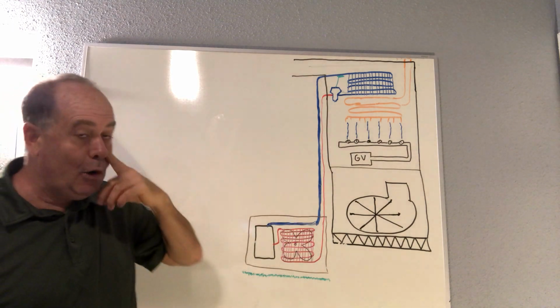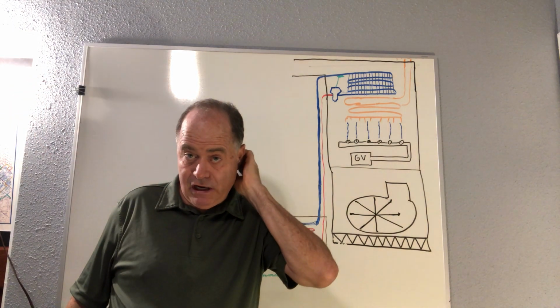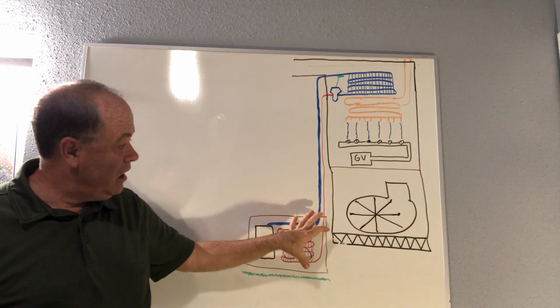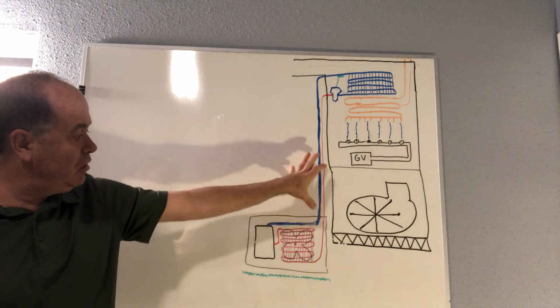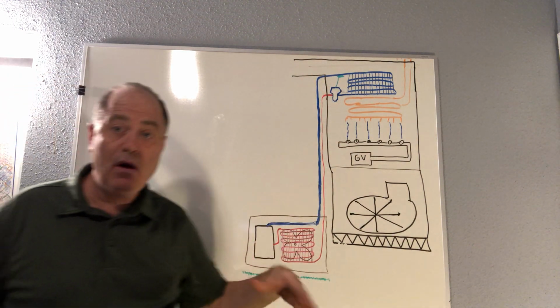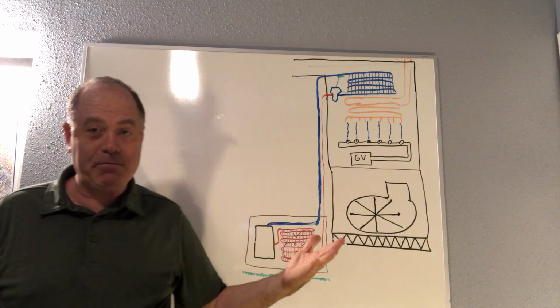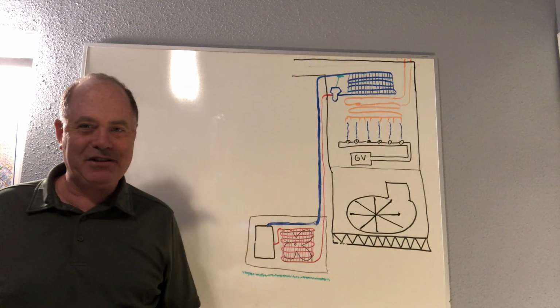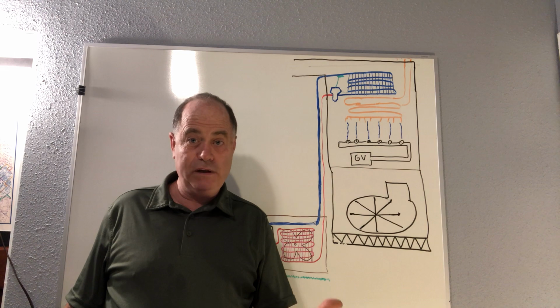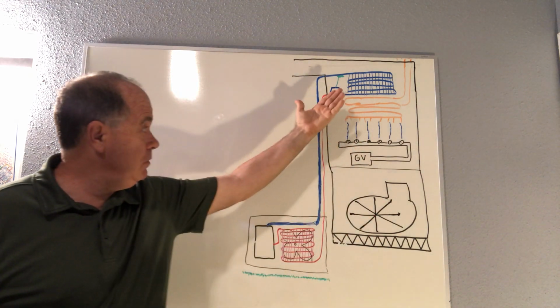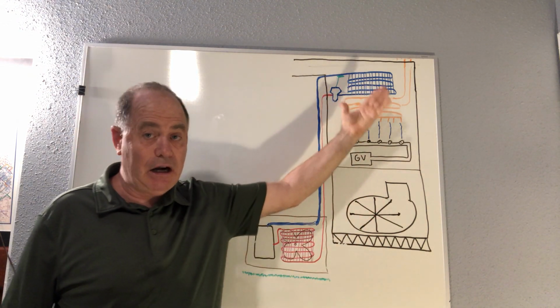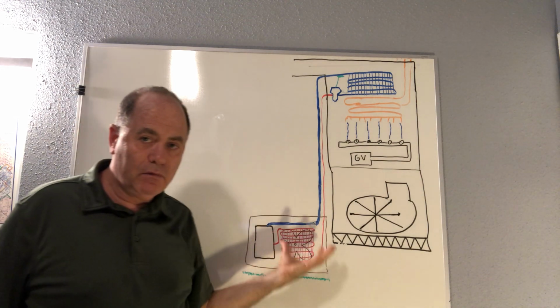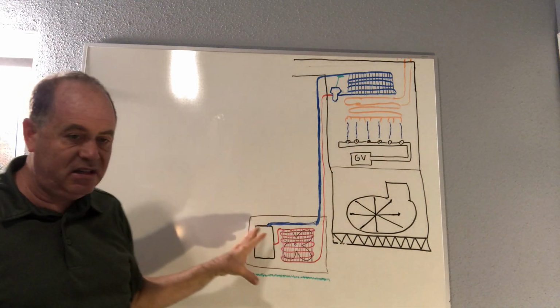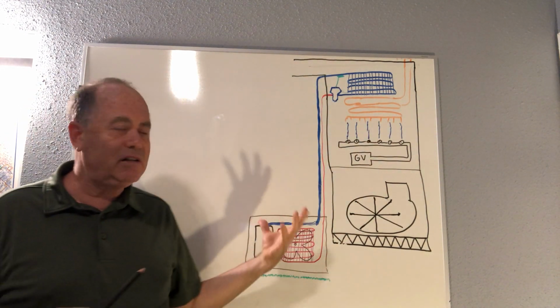because it's going to be colder outside when you're running the heating, right? The refrigerant's going to be flowing here, going to this lower pressure now outside, and actually your evaporator will be under a higher pressure than your condenser. Did you think of that? When it's cold outside, when you're running heating, your evaporator will be at a higher pressure, and you'll end up with this unit out here tending to dissipate it. Okay, so a lot of times it's acceptable, but you'll still end up with a pretty high pressure.